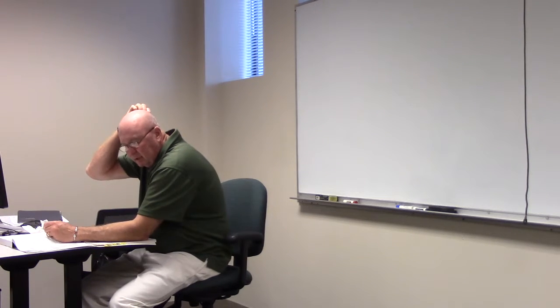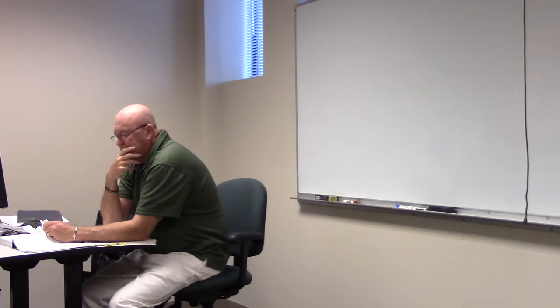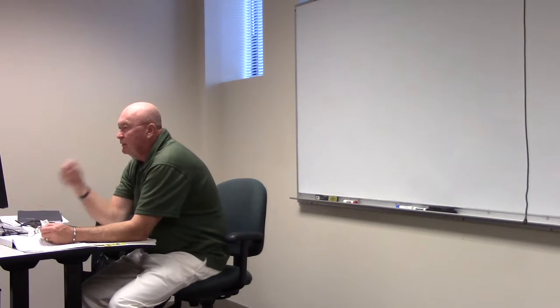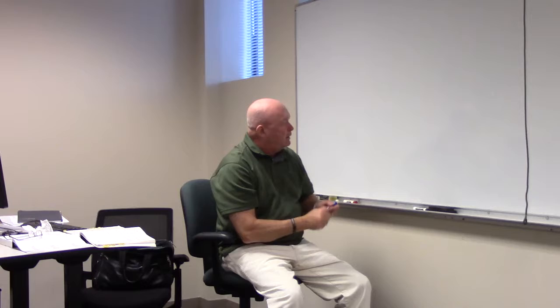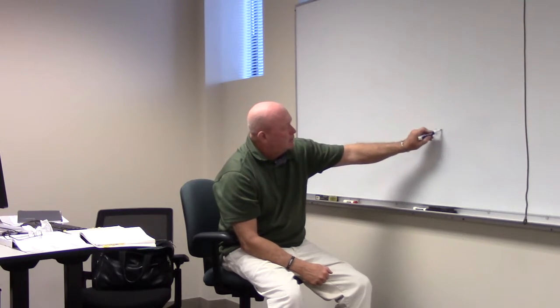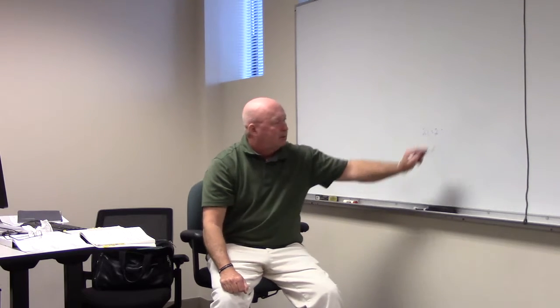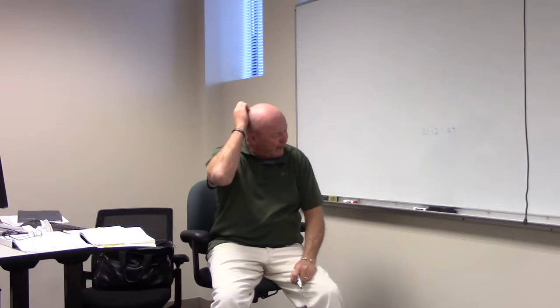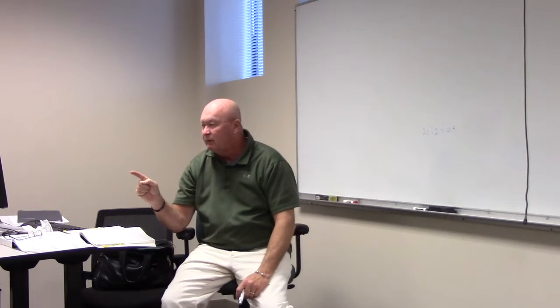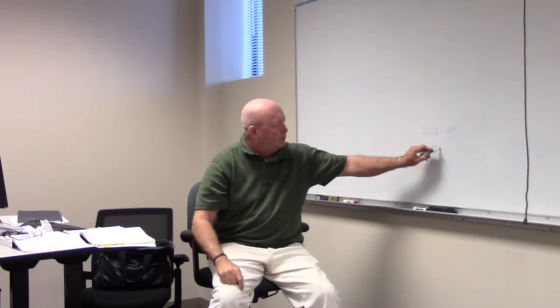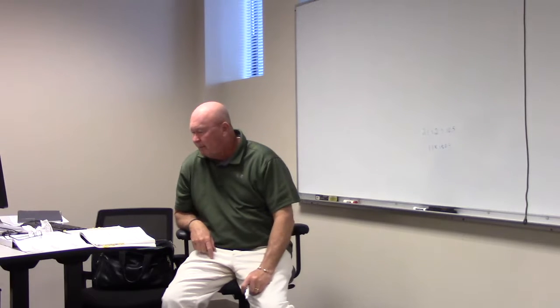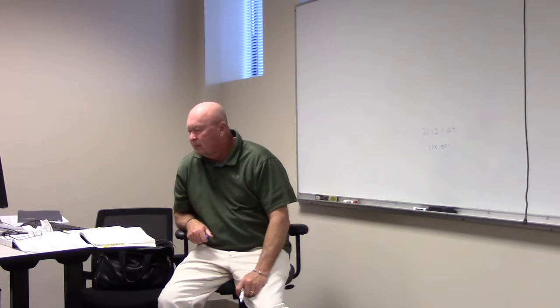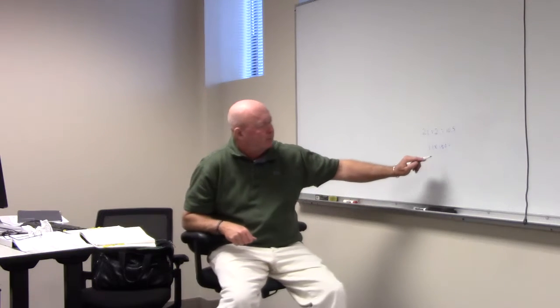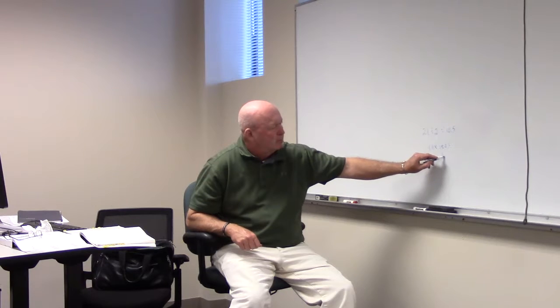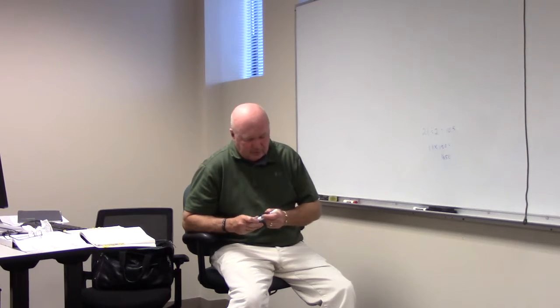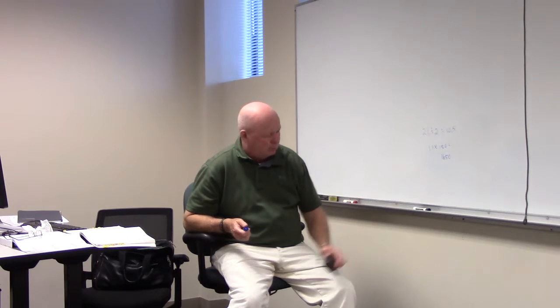Example number 2 said if you got 21 foot of track, what would you do? You take 21, you divide it by 2, it gives you what? 21 divided by 2 is what? 10.5. But really, because it's 10.5, what is the multiplier going to be? 10 or 11? 11. And we do 11 times 150, is that right? How much? 1,650 volt amps.